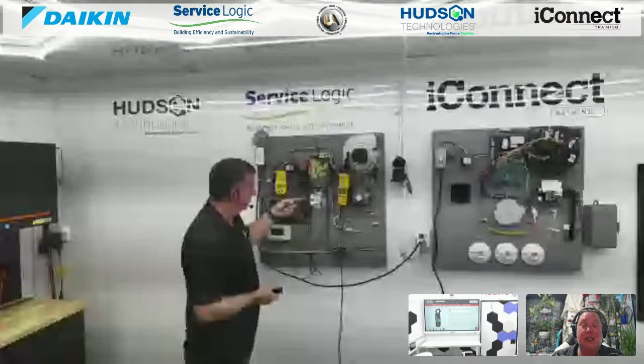And then what is on the top number? So that top number is actually your power factor. Power factor is basically a percentage, and it's telling you how efficiently it is actually using that wattage. So you mean this shaded pole motor is only like 30% efficient? I mean, it's highly possible - that's about right, actually. So our shaded pole motors are very inefficient. For those instructors with us, this is a fantastic way to show different motor efficiencies, because we can actually look at the true wattage draw of that motor, and then we can start looking at those power factors, and we can see the efficiencies that change through those.